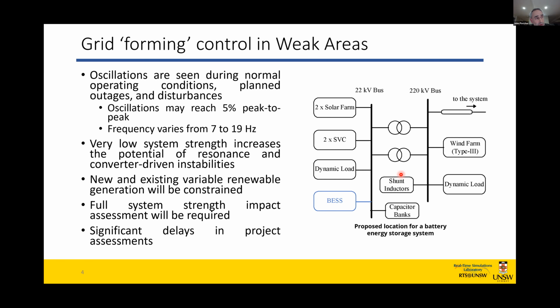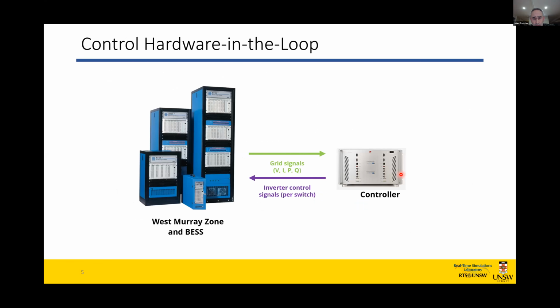And we looked and helped an organization who owns some of the assets out in this area of Australia. And we looked at using a battery energy storage system with a grid forming control capability on the inverter. And what we did was basically we took the control hardware and put it in a hardware in the loop system. So fairly standard approach.